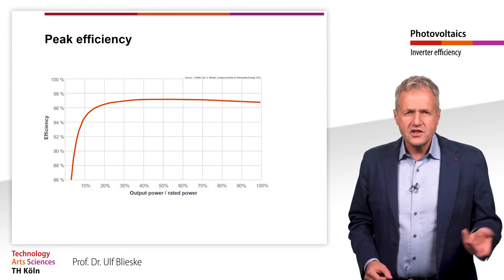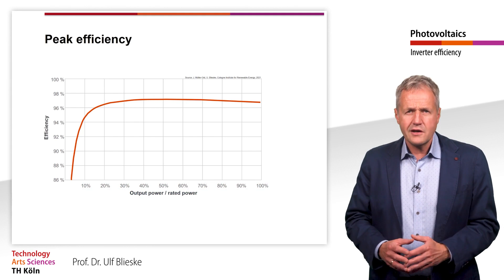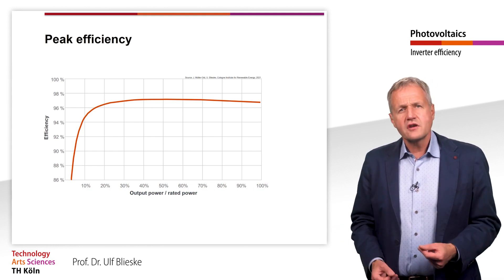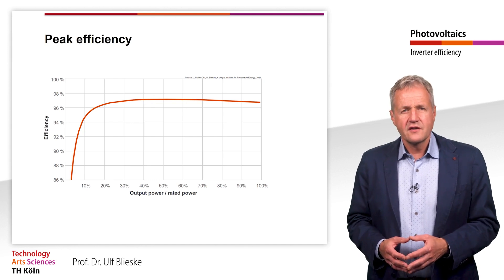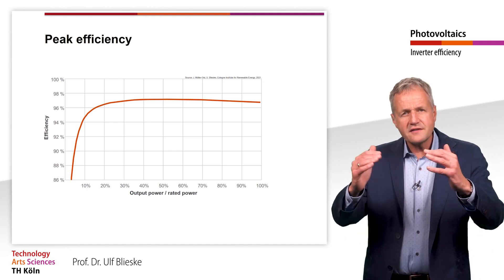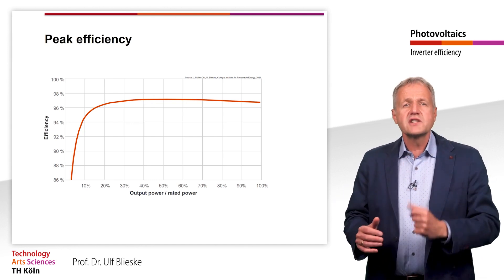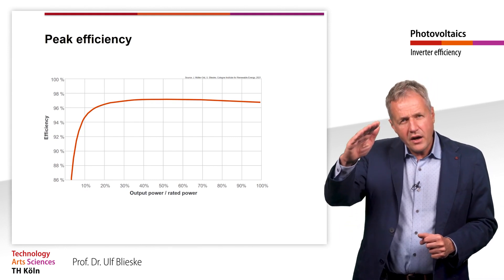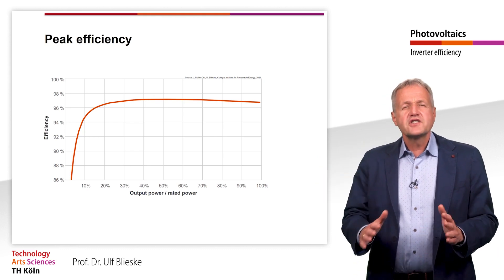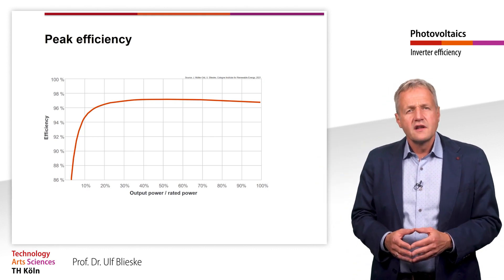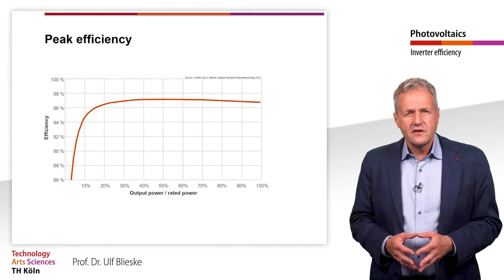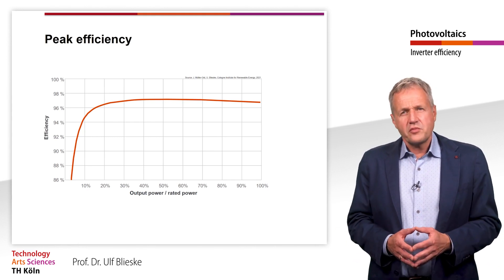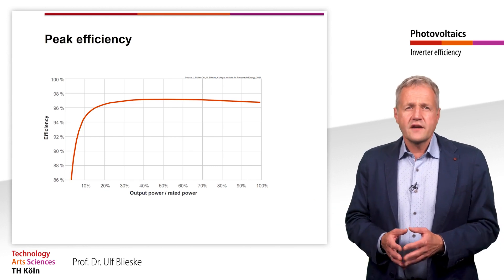At 50% it delivers only half of its rated power, and so on. It can be seen that the efficiency is very low at low power levels. This is mainly due to the self-consumption of the power electronics. As the power increases, the efficiency increases and reaches its maximum at about half the rated power. At higher input power, the efficiency drops again somewhat, due to ohmic losses which increase exponentially or squared with the power.